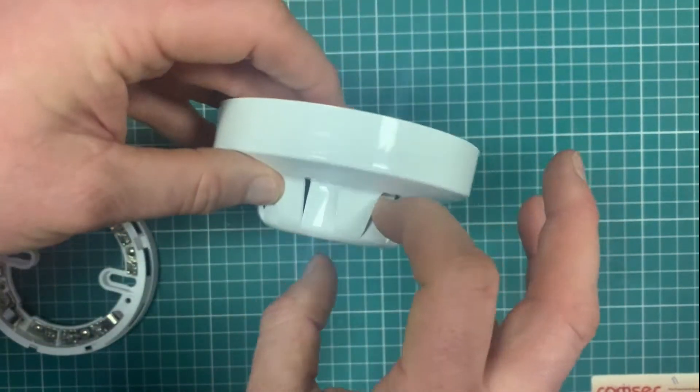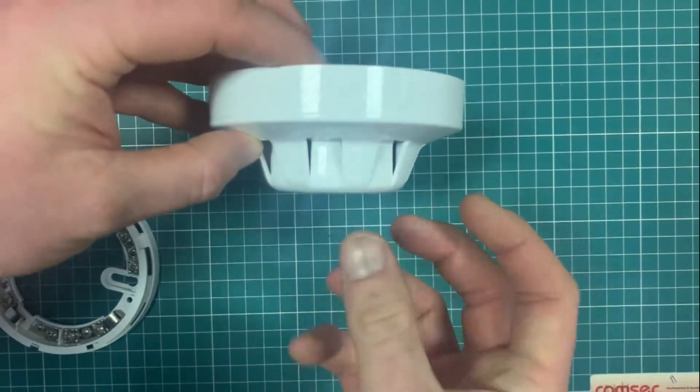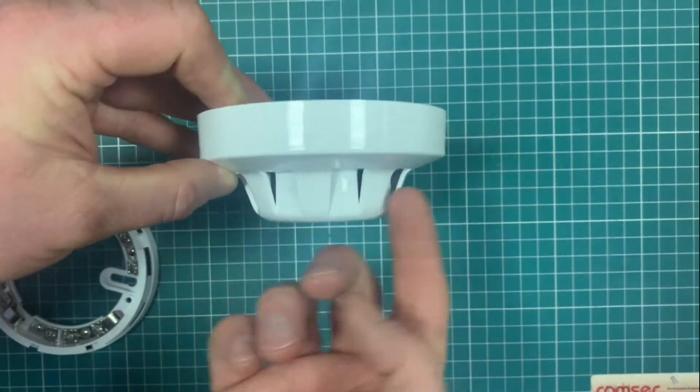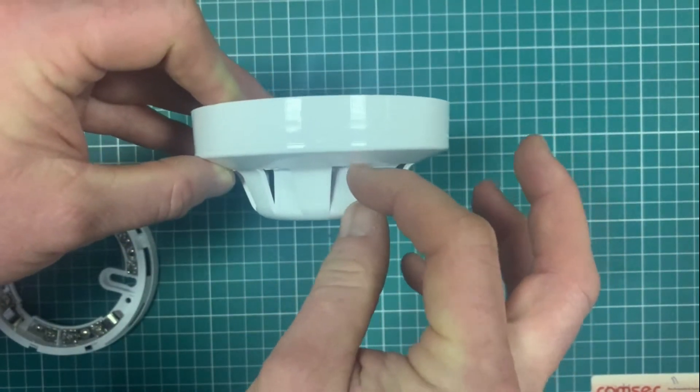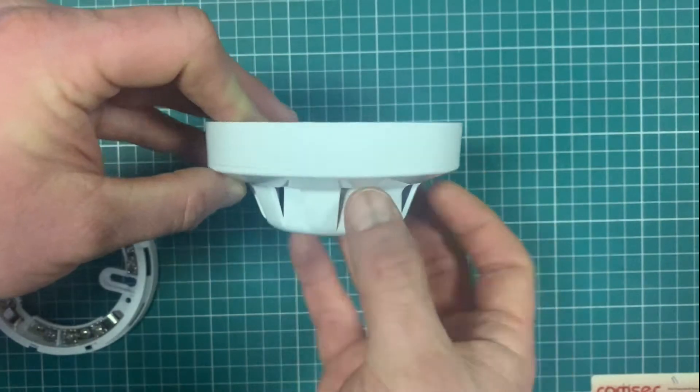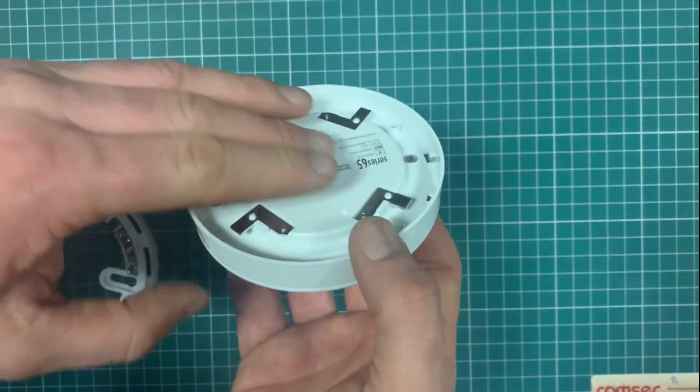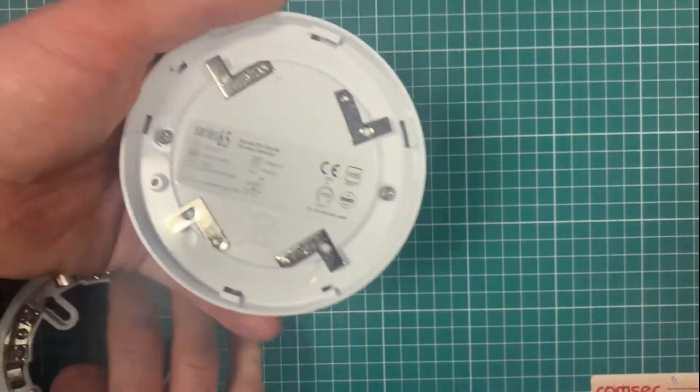The smoke goes in through here. There's an optical chamber inside the detector. Basically, the optical chamber is looking at the percentage obscuration of the light within this chamber. It sees a reduction in the light between two points, and based on how obscured the light beam is, it tells the detector to trigger and set off your alarm. Fairly basic stuff.